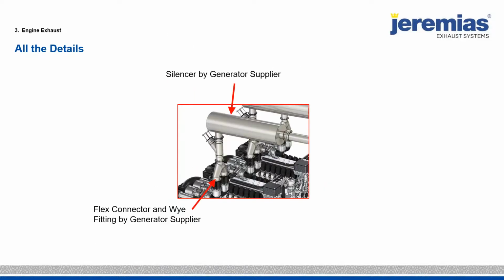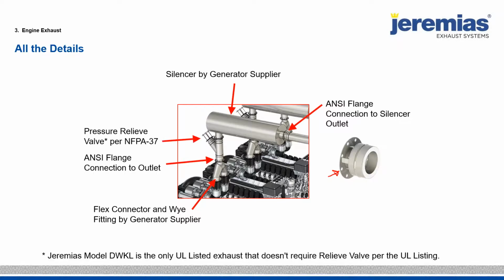First, we supply the ANSI flange connections. So this is a stainless steel plate, which is mounted directly to the ANSI flanges. We actually make a stainless steel relief valve, but I want to make a note that Jeremias is the only UL listed system that does not require a relief valve. That's because of our pressure rating and the way we stiffen our elbows. So we do not require a relief valve like Schedule 40.